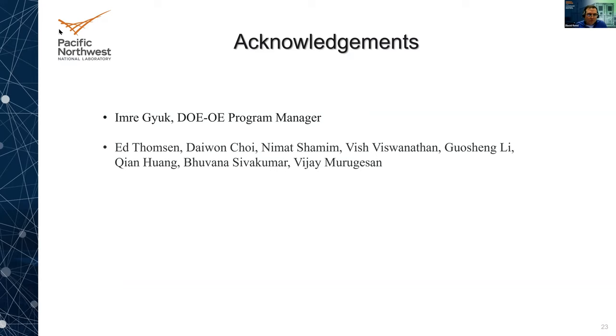Thank you, David. I want to encourage additional questions in the chat — we'll start the question and answer period now. A few questions came in about lithium ion testing and our temperature capabilities. We do have environmental chambers for smaller scale stuff. We could load a module into an environmental chamber if needed. The expectation is as we move to the grid storage launchpad with more room, we would have that temperature capability for larger scale.